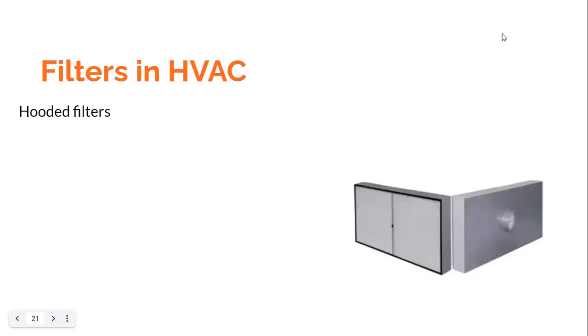Finally, we discuss hooded filters, which are used in clean room terminal filtration applications. These are terminal filters that also carry a small individual supply air side plenum with airflow control dampers that can be operated from the outside. The hooded filter has a collar that can be used for connecting the supply air duct, and hence they are used in terminal units. This concludes the general discussion on filter types based on construction methodology. See you in the next lecture.